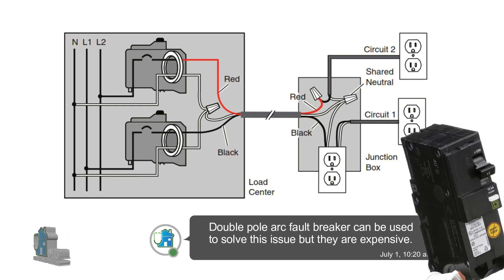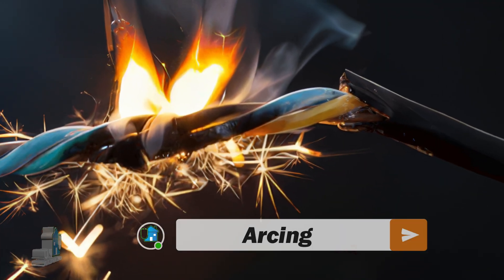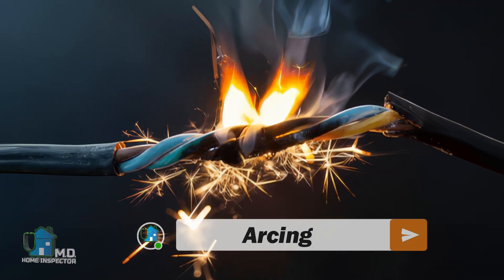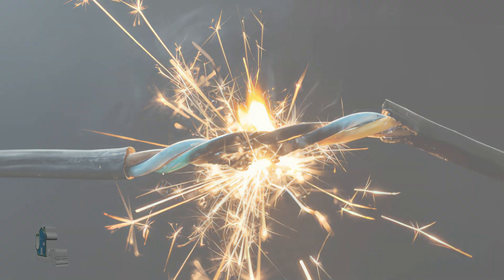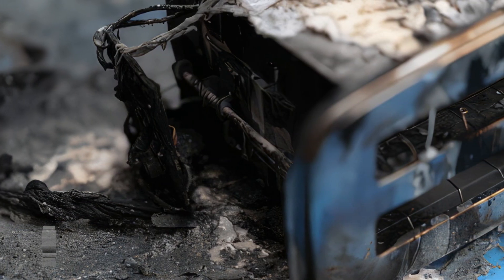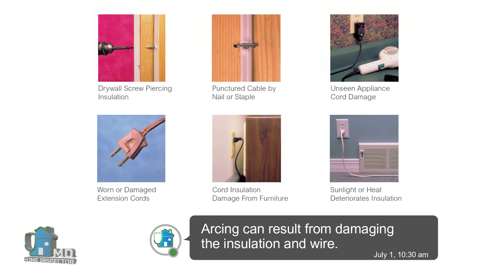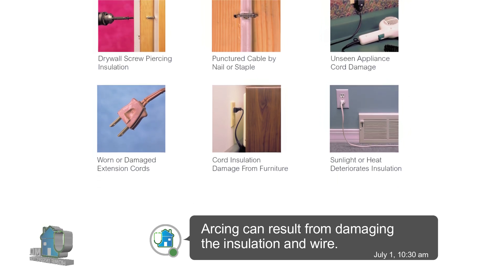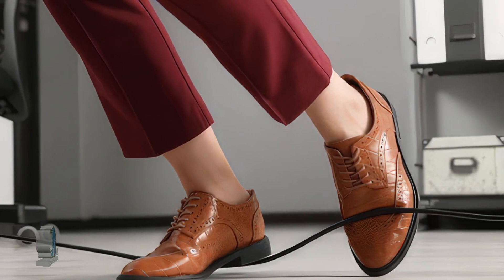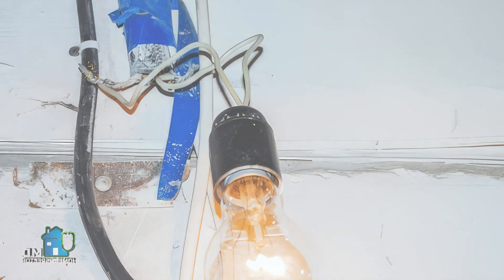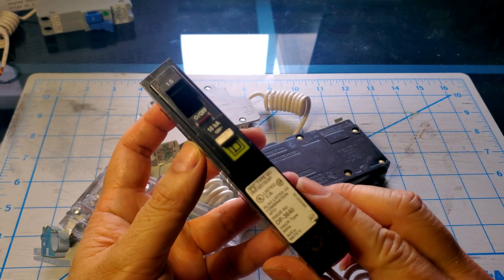Finally, there is dangerous arcing. Arcing is a luminous discharge of electricity resulting in extremely high temperatures that can ignite materials around the wire, causing a fire. Arcing can result from punctured cables from staples, screws piercing a wire, damaged wires, or extension cords — particularly vulnerable from careless use such as walking over them. Arcing from loose connections is also a common problem.